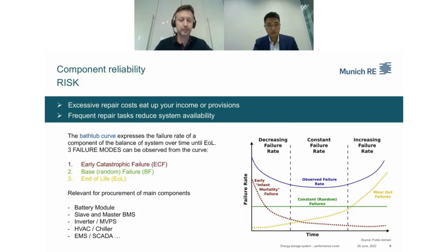To assess this risk, we rely on the experience of manufacturers, our own databases and calculation methods, as well as field tests or third-party analyses. In most cases, it is sufficient to limit the insurance cover to the main components mentioned on the left bottom of the slide: the battery module, slave and master BMS, inverter medium voltage power system, the HVAC and the chiller, which is the thermal management system of the asset, and the EMS and SCADA. That accounts for more than 80% of the investment.